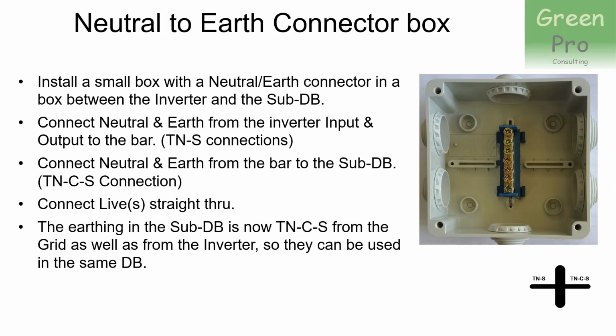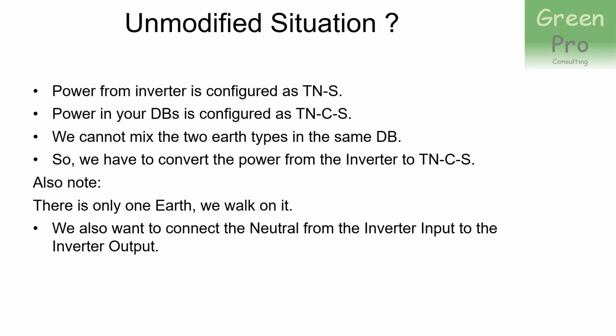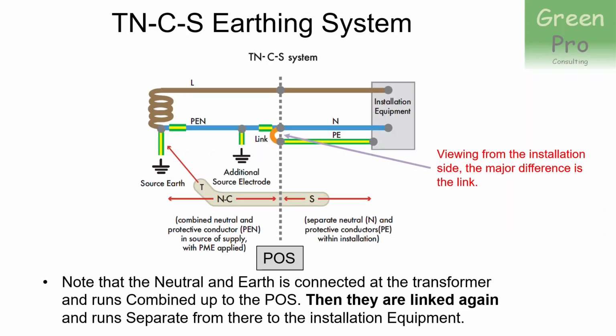So there's 3 wires really. It's a neutral going into the inverter, call it from a sub-DB, because that's what you often have that sits next to the DB. You connect the inverter input and the output neutrals to the bar, and you connect the earth to the bar. So there's 3 wires going to that little bar. Then you connect the neutral and earth from the bar to the sub-DB. And that is then your TNCS connection, because the bar, if I go back up, now becomes that link.